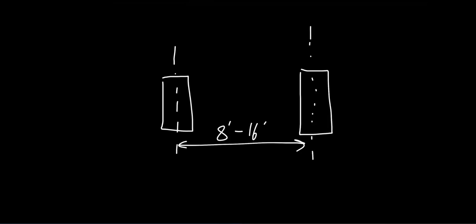Now let's look at how active beams should be located relative to each other and how other obstructions might affect their performance. Beams are generally positioned at centers between 8 to 16 feet apart, depending on the loads of the building. If the room has just a single beam, it is often positioned parallel to the glazing or in the center of the room.